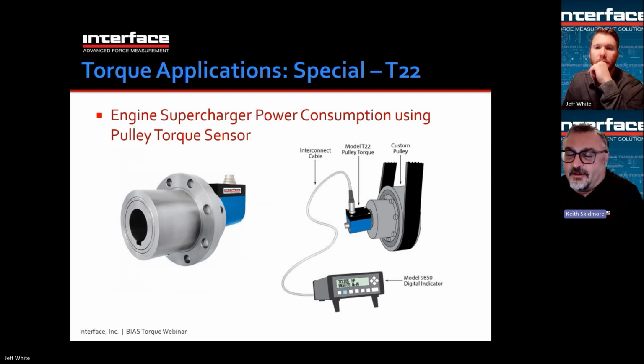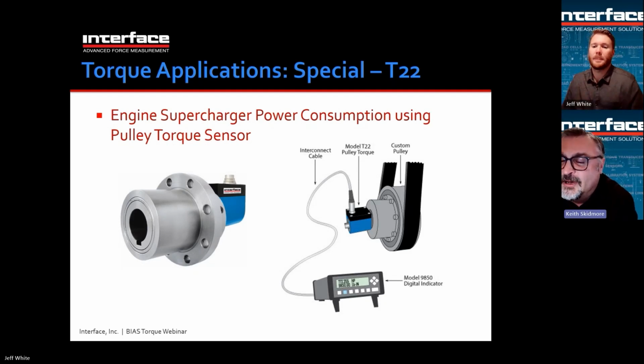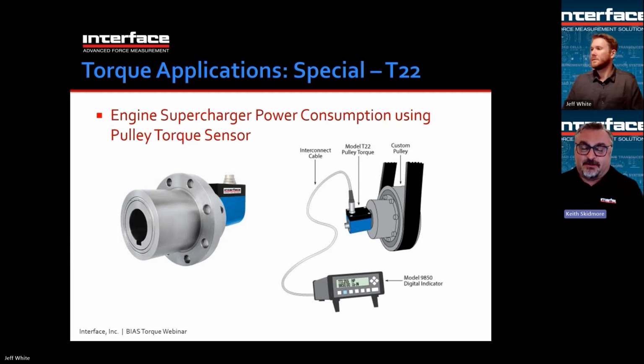Here's an example I mentioned earlier, this model T22. Basically, you have a pulley on the end of a motor shaft. You can take that pulley off. You can make a special pulley that mounts onto the T22, and then you mount the entire T22 onto the motor shaft. So the T22 has a bore, which you can see on the left side. It is keyed. And we say we don't like keyed hubs. Well, this type has to be keyed because you really can't make this hub grip onto a shaft, because there's no method for doing that. So it's a keyed hub that slides onto a shaft, and then the pulley mounts to the bolt circle that you see on that torque sensor.